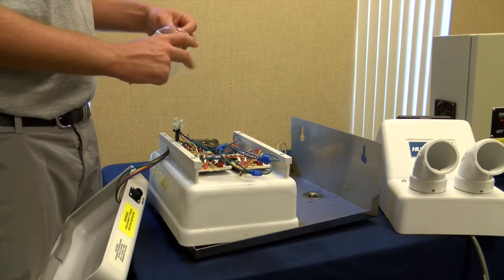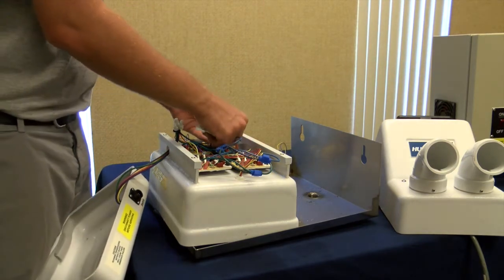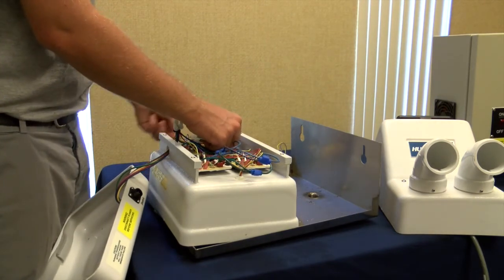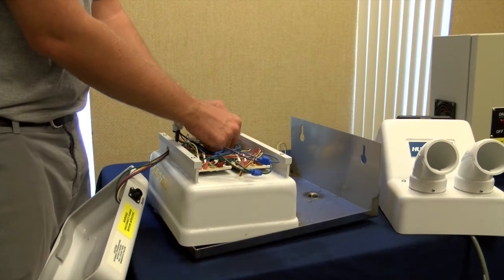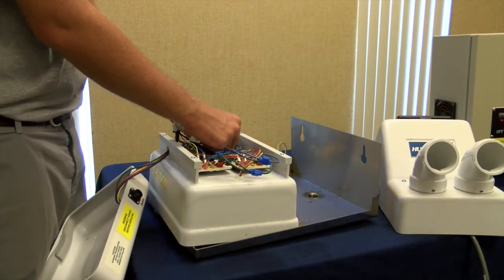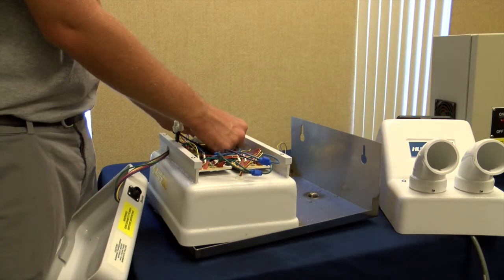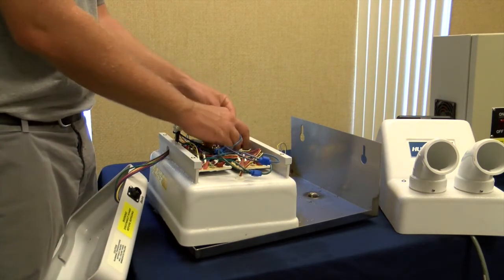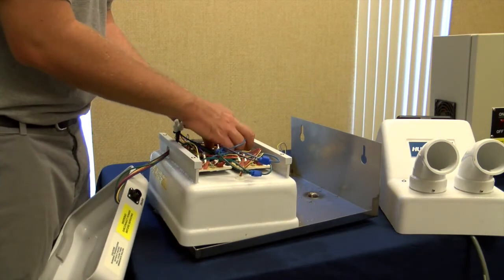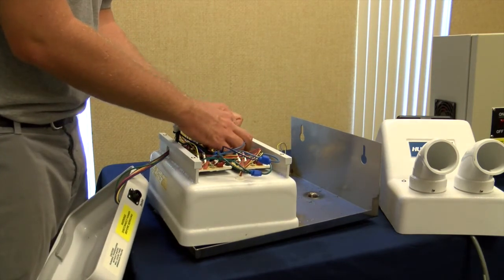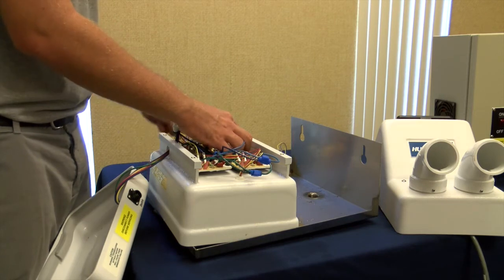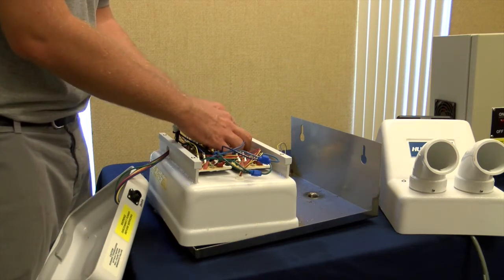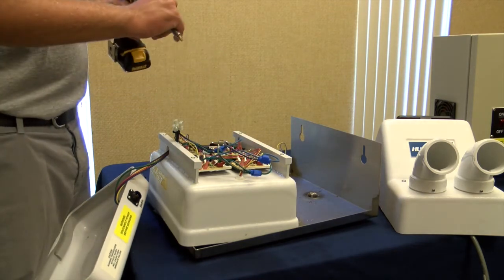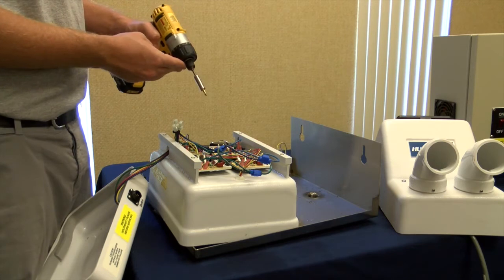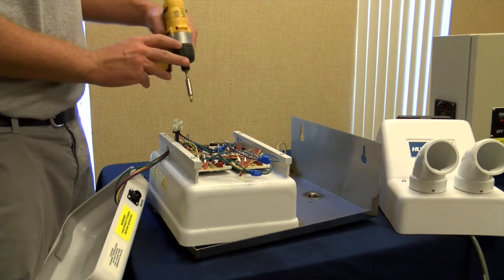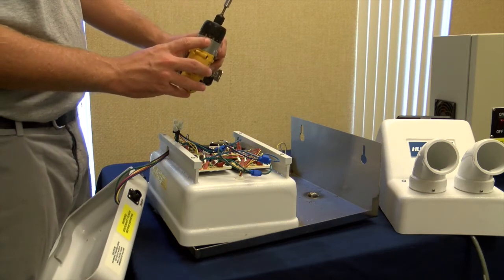Then to replace, you'll simply take your new one and put them back in the same place. The long screws are used for the transducer. The short screws are used for the print plate. When tightening them down, be sure not to use too much force. We recommend on our drills to use a number 4.